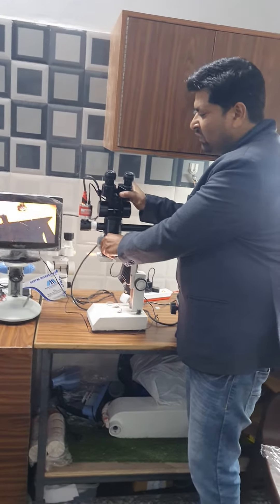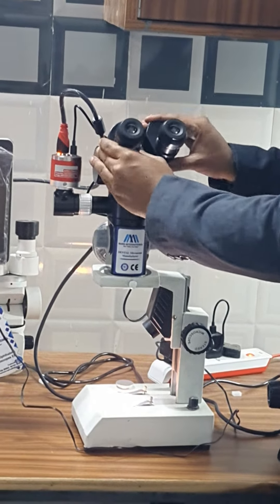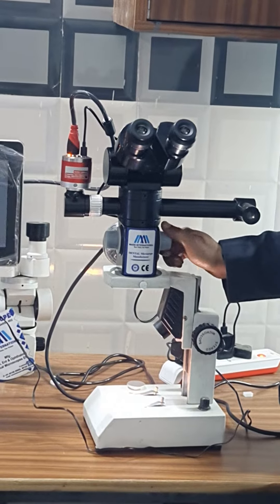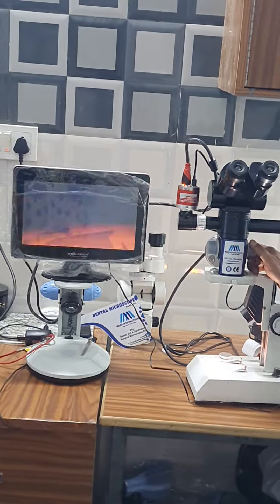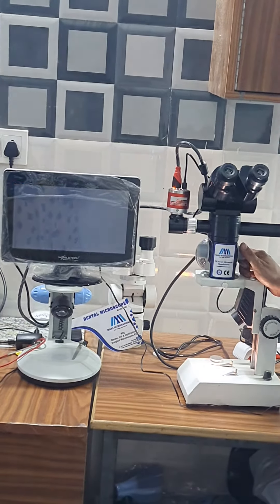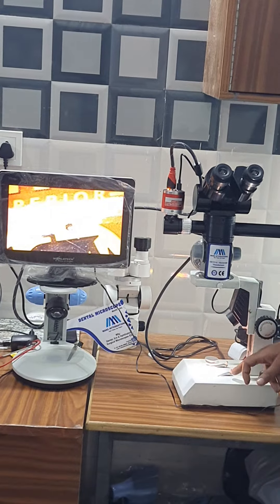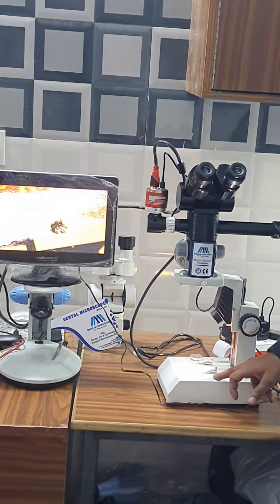It is moving 0 to 180 degrees. IPD you can adjust. 12.5X eyepieces. Magnification you can change from both sides — it is 2.5X, 10X, 6X, 4X, and 16X. Its working distance is 250mm.